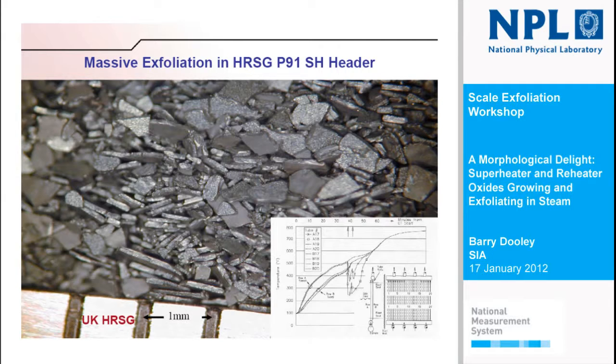In HRSGs, sometimes they have very severe thermal transients because of condensate coming back into the header when the unit is starting up. You can see an example of an HRSG start-up where at a certain point the condensate comes back into the cycle and you get a very large thermal transient — this can be over 300 degrees instantaneously. Occasionally we see oxide like this in P91 headers in HRSGs. In this case, a little unusual, maybe because of the very severe transient, we just get the duplex pair exfoliating.